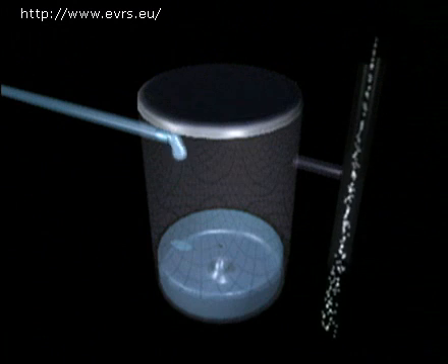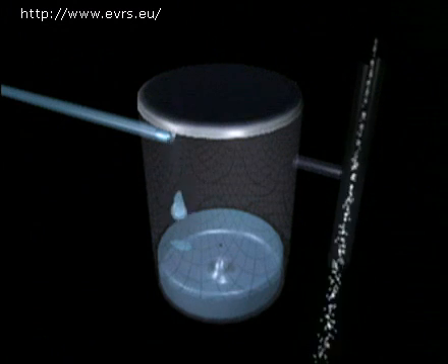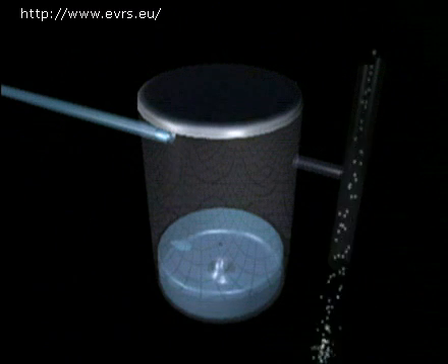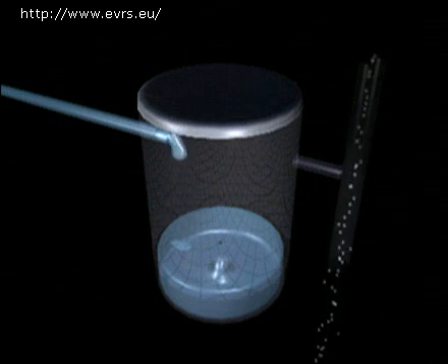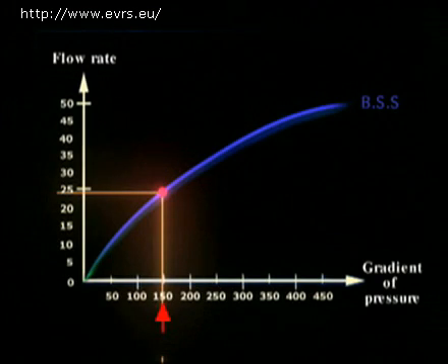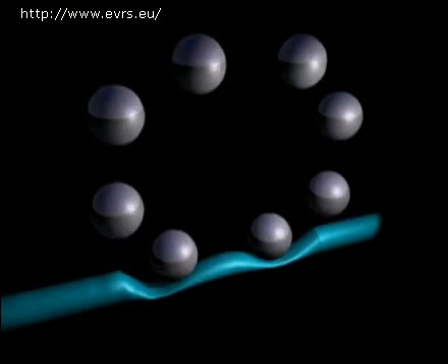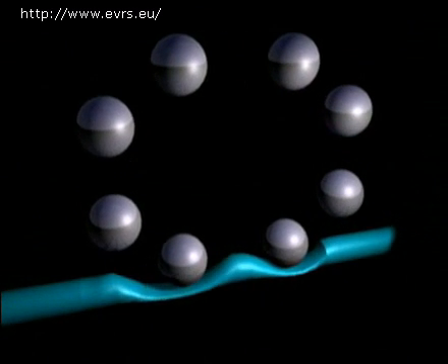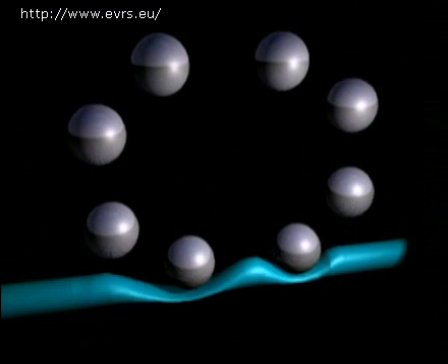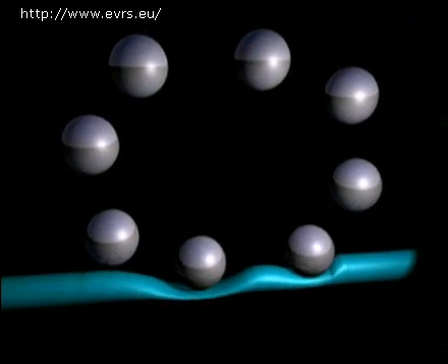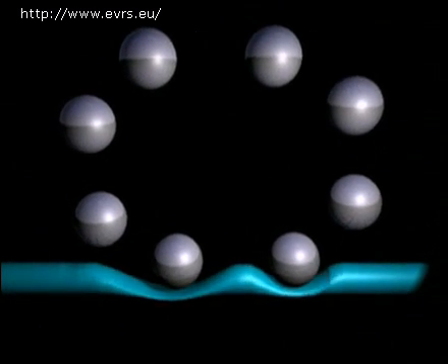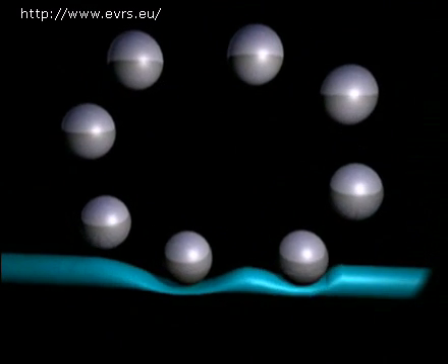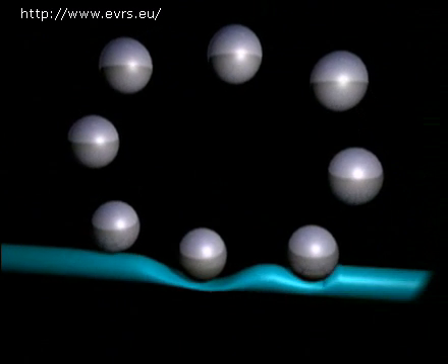When using a pressiometric pump, like the venturi pump, the operator selects the desired depression with the foot pedal. The gradient of pressure obtained by the difference between the depression at the pump level and the intraocular pressure will create a certain aspirating flow. With a debimetric pump, like the peristaltic one, the operator controls the speed of the rollers. At each turn, the roller expels a certain quantity of fluid from the tubing. When returning to its rest position, the tubing creates a depression that will aspirate the column of fluid by the same amount as that which was expelled.